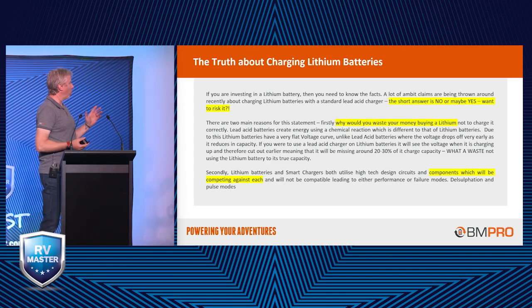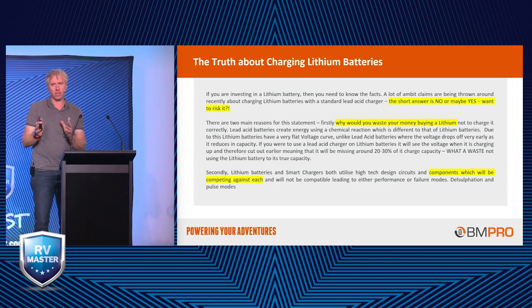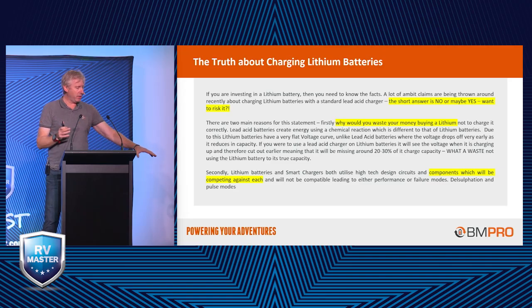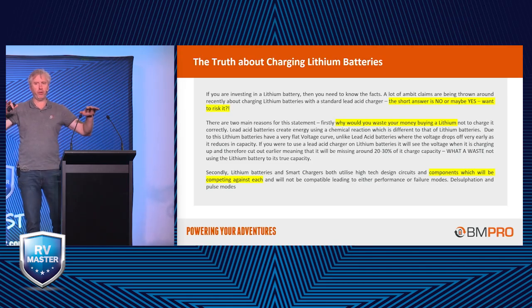The other big reason why you want a dedicated charger with a dedicated profile - and this is really important - is that inside the lithium battery, as I mentioned before, it's got electronics, the battery management system, with high-quality, top-end processors, microprocessors, and semiconductors. In the battery chargers, there's the same. If those two are competing against each other, in a lead-acid profile you'll have things like pulsing modes and trickle charges, where it switches on and off. Well, the BMS is not going to like that, so they're going to start competing against each other.